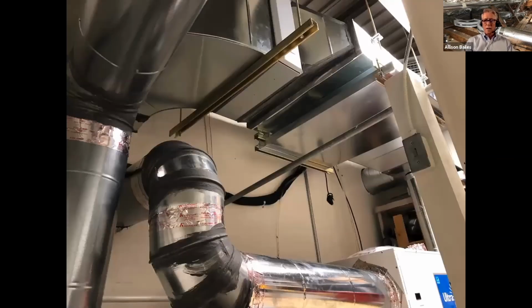All right, so let's see. This is the system in our office. So this is a 12K, 1-ton Mitsubishi SEZ unit right up here. The air handler's right up there. We got a transition piece here going to a filter right here. And then we've got a big radius turn right here. And again, there's the throat, nice radius throat with a good radius of curvature relative to the diameter of the duct. So low equivalent length, low pressure drop, radius turn there.